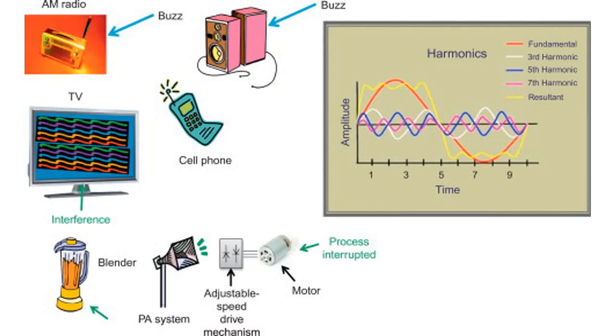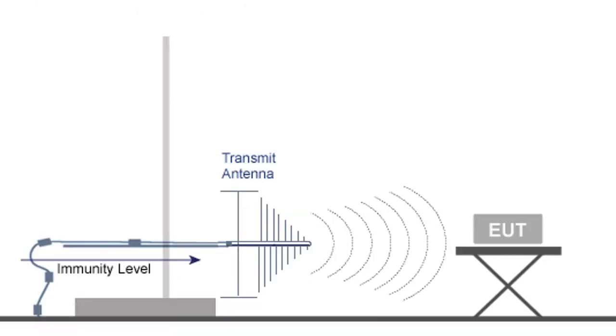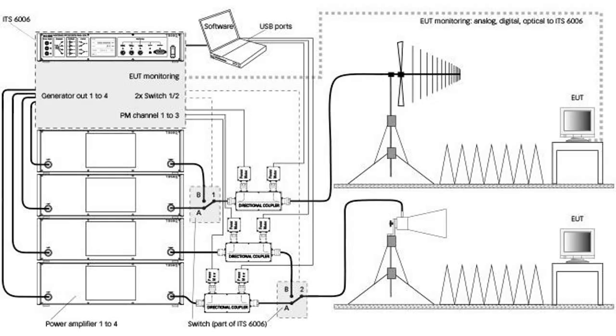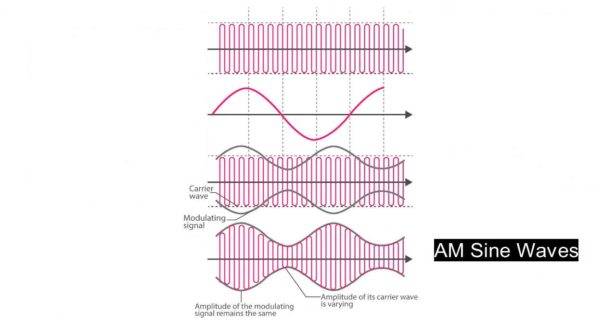Now we will discuss immunity tests. A product should be expected to work as intended correctly in any environment that they are reasonably likely to encounter. RF immunity: in order to test equipment for its immunity against RF signals, a defined signal needs to be generated and coupled into the EUT. Due to the nature of the signals and their means of transmission, various transducers are defined by the relevant standards for various testing methods. The base signal for all RF immunity tests is a sine wave signal, which is then modulated in different proportions and applied to the EUT.